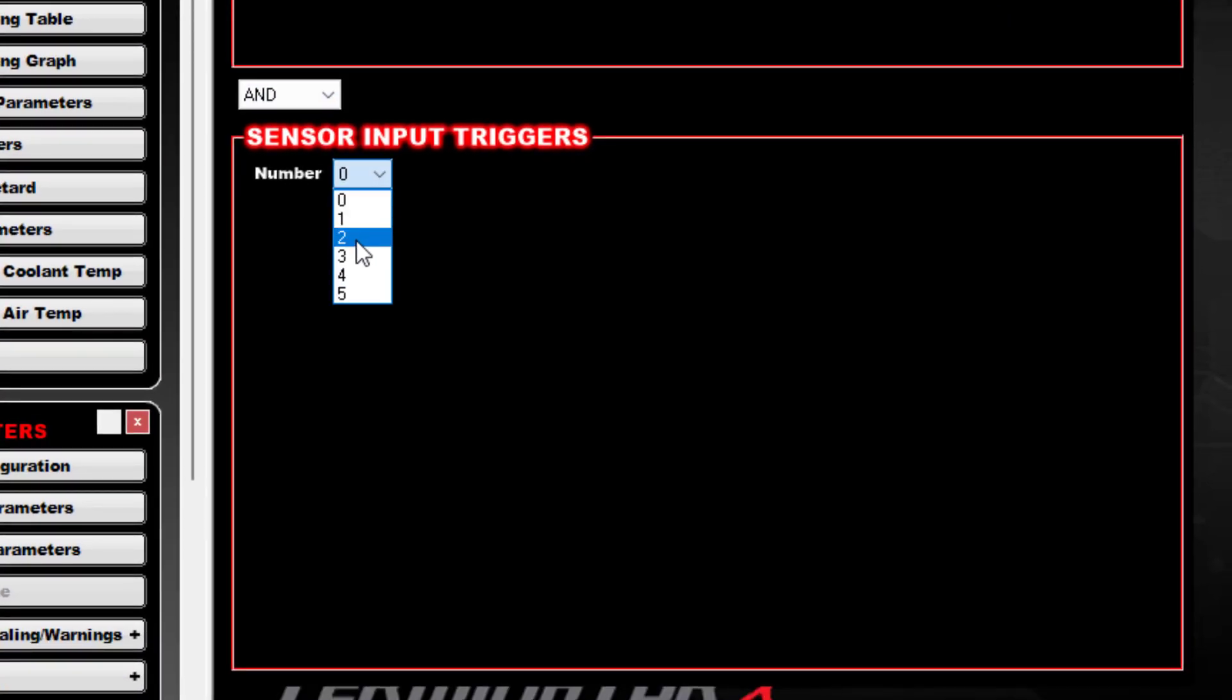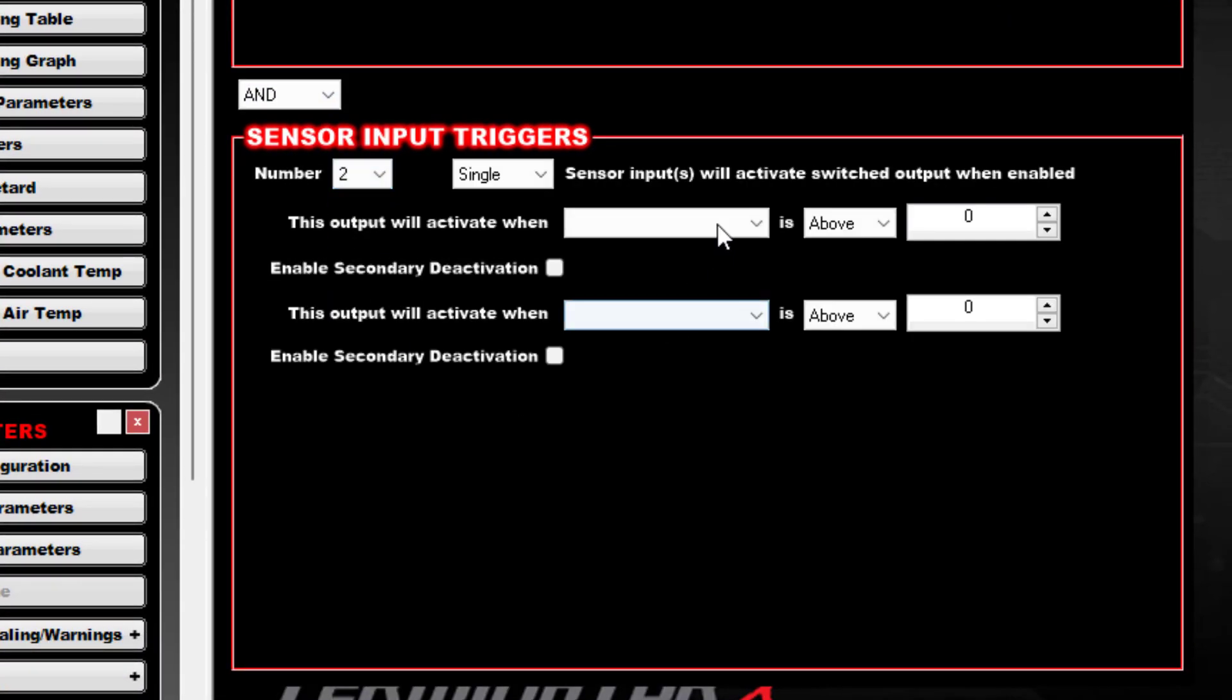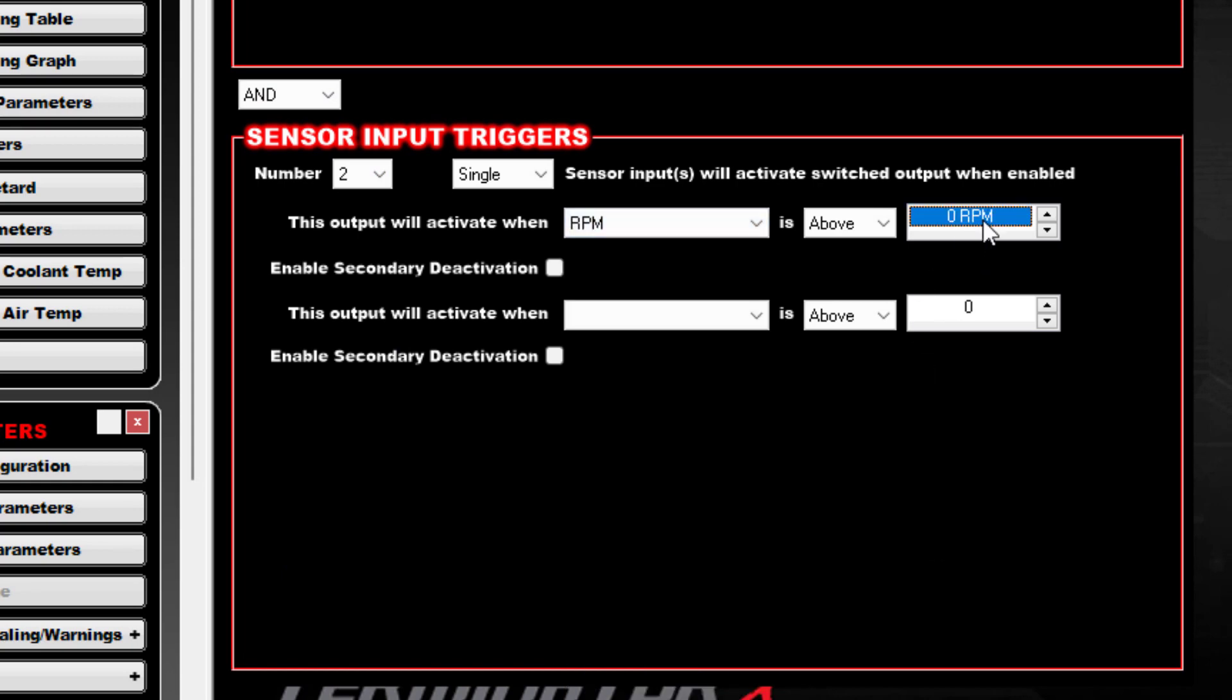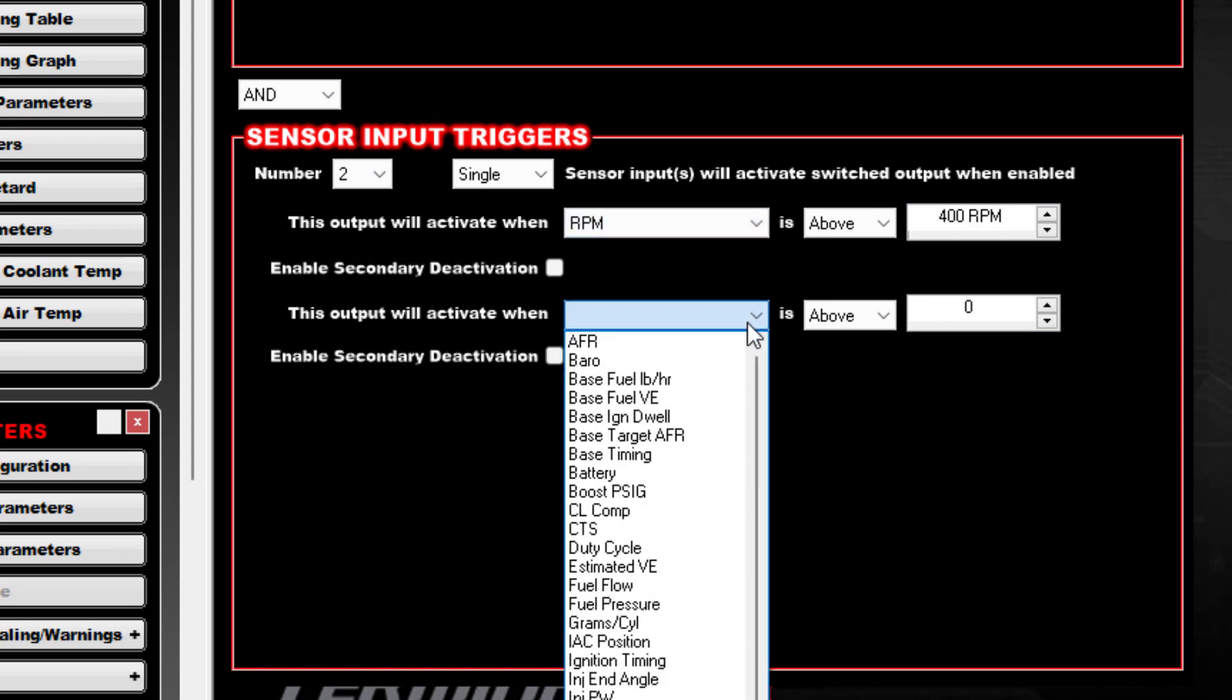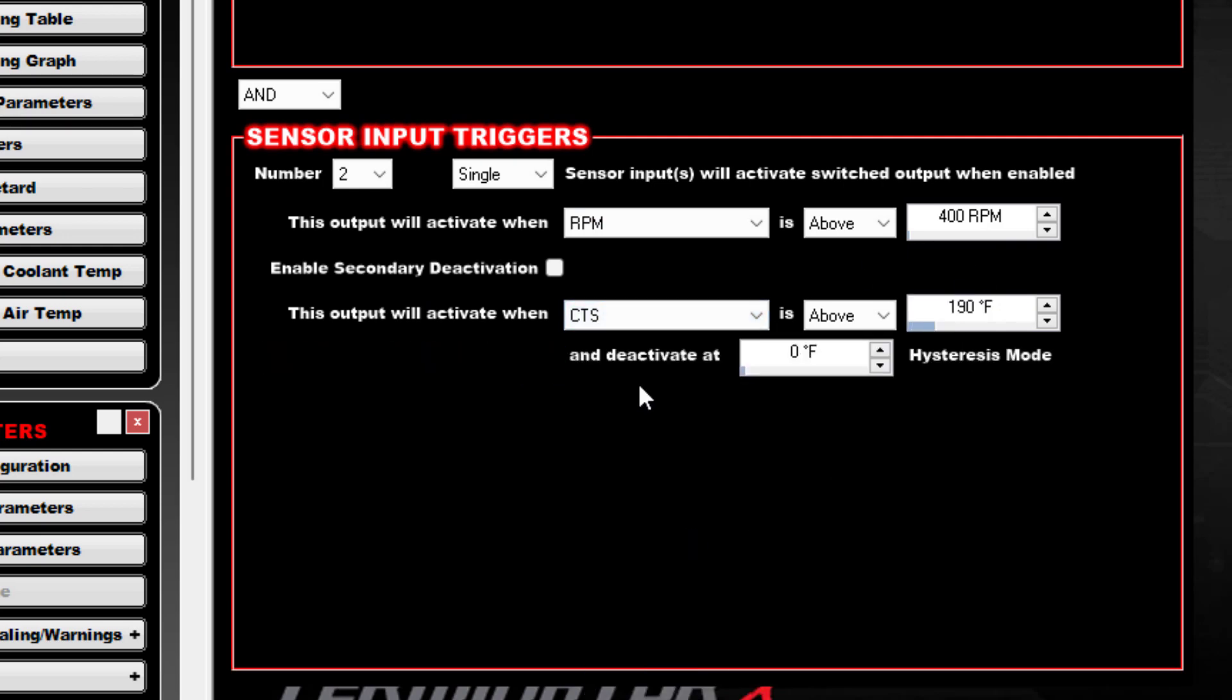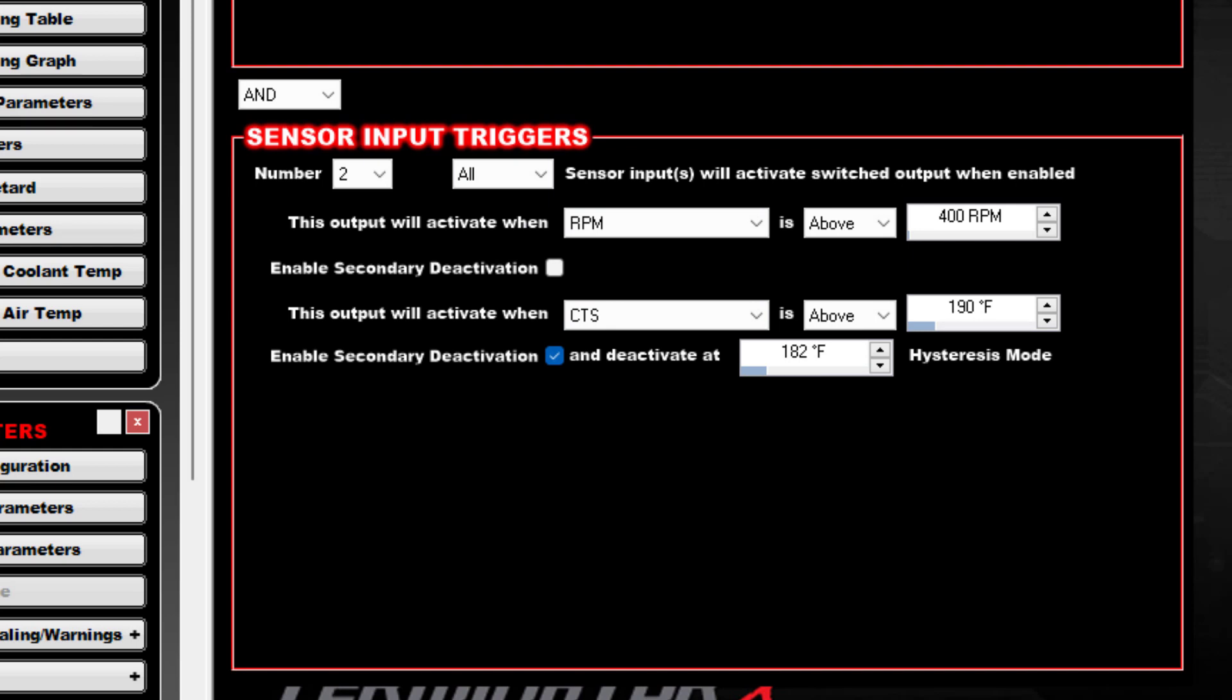We're going to set this to two. We'll set the RPM above 400, and we'll set the coolant temp for this one a little bit higher. We'll just say 190 and kick it back off if the temps fall back below 182. Set this to All also. So this gets us at least to that point where you've kind of done what the factory logic is doing with one exception.